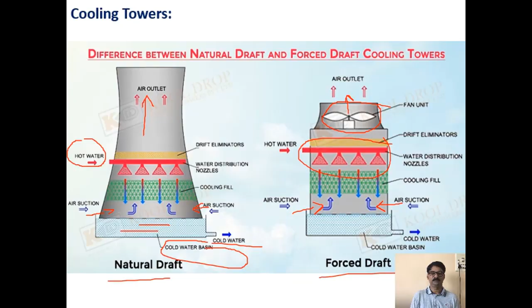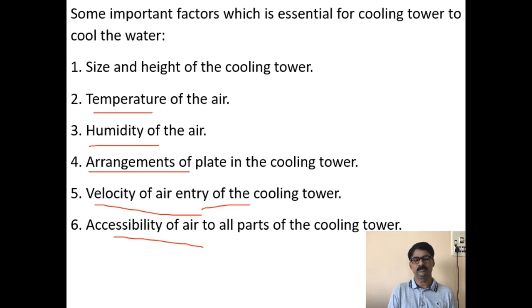Some important factors essential for a cooling tower to cool the water: the size and height of the cooling tower, temperature of the air, humidity of the air, arrangement of plates in the cooling tower, velocity of air entry into the cooling tower, and accessibility of air to all parts of the cooling tower. The water which is sprayed at the top or some mid height of the cooling tower passes through many plates placed in between. It falls on these plates and comes down slowly because it should not fall at once. That is why some plates are arranged horizontally inside the cooling tower. The velocity of air entry also plays an important role, and the air should be accessible to all parts of the cooling tower so that hot water gets cooled from all the regions.